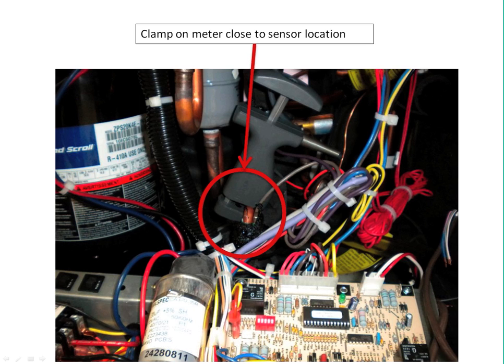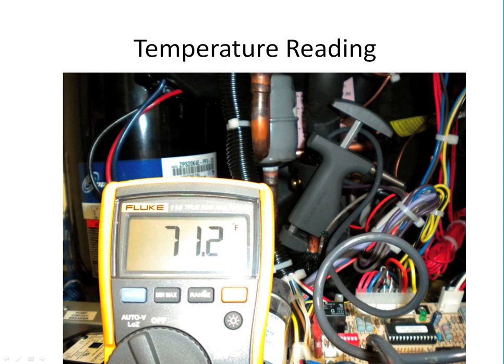So, how do you do that? Well, if you suspect a thermistor, you want to take your attachable temperature display thermistor from a Fluke or whatever kind of a digital meter you have. You want to attach it firmly onto that copper tubing right next to that thermistor. You can see here on the screen that example. We have that attached right next to where the thermistor is. Next, you want to run that system. Again, give it that good 15 minutes of runtime, see what's going on there, and when it starts to stabilize, go ahead and record that temperature. So we're showing that thermistor temperature from our digital clamp on to be 71.2 degrees.